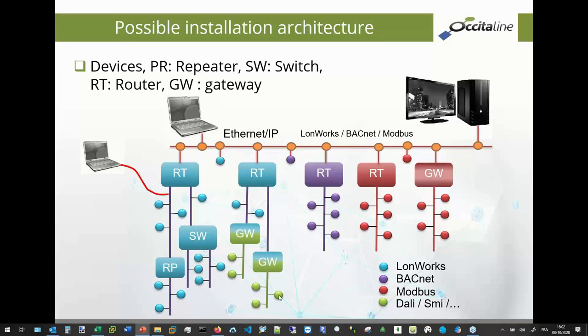What is the installation in reality? In reality, on field you always have devices on field and devices on IP. A repeater for increasing the distance and the number of devices on a channel. A switch, which is a little different from a repeater, and we will see that just after. The router, which filters some addresses, and the gateway. The gateway converts a protocol to a second one.